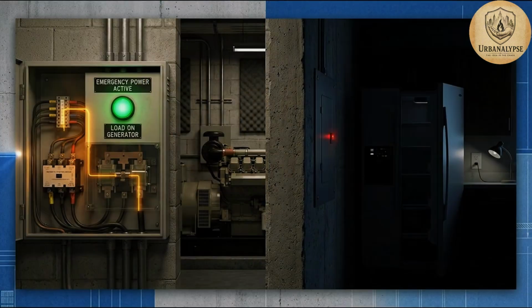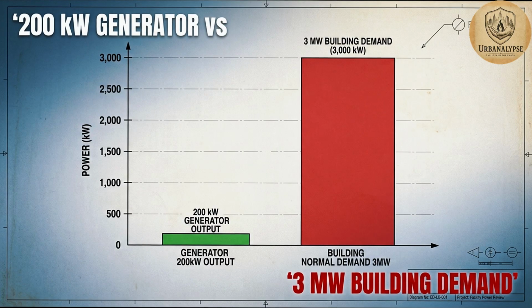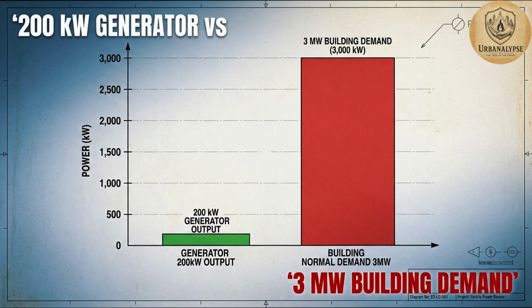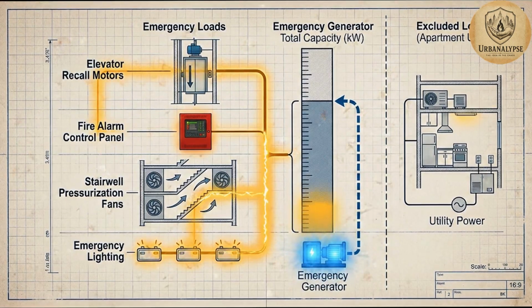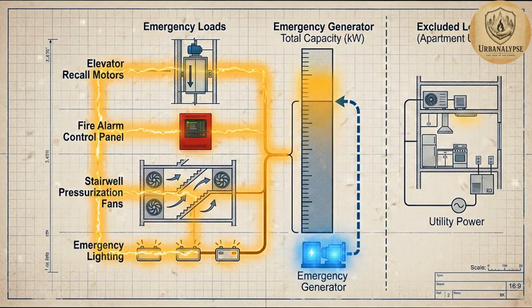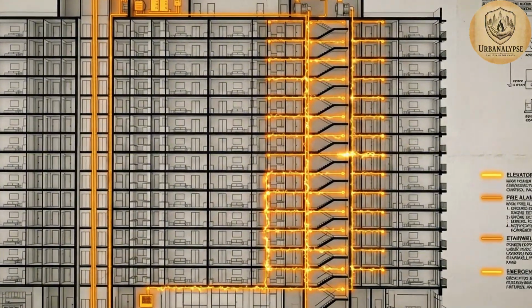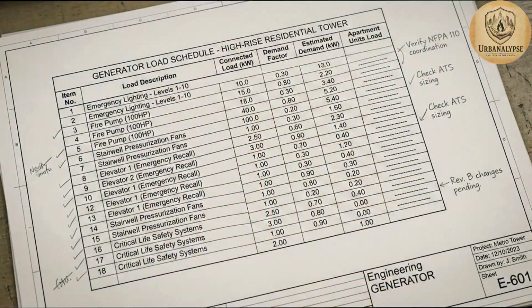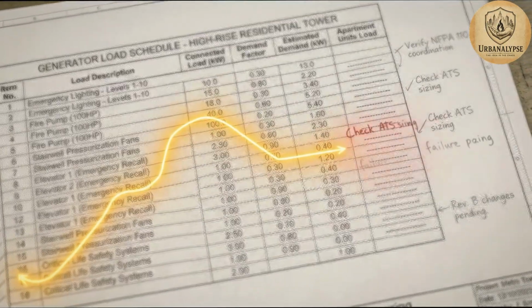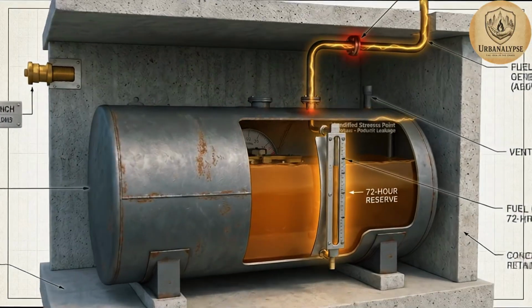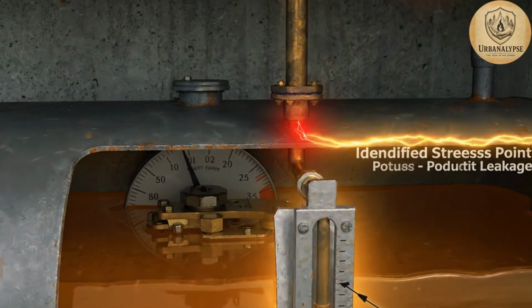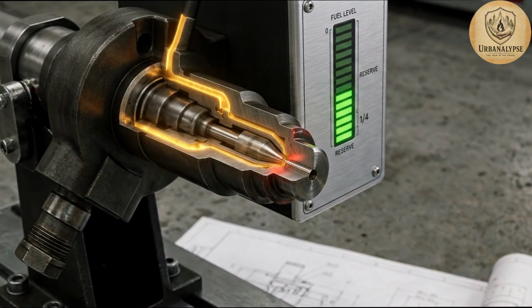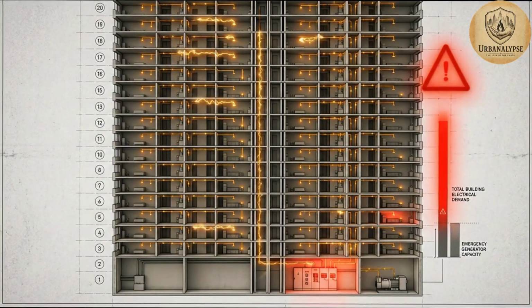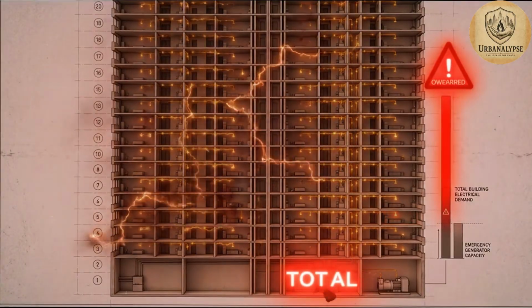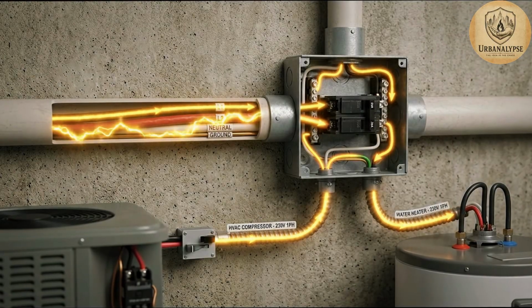Generator sizing standards for commercial high-rise: typical 20-floor emergency generators are sized for approximately 150 to 250 kilowatts of dedicated legal load. Enough to run elevator recall motors, fire alarm control panels, stairwell pressurization fans, and code-required emergency lighting, but only a fraction of the 2 to 4 megawatts a fully occupied 20-floor building draws under normal HVAC and appliance demand. The math itself is the exclusion mechanism, a generator engineered to sustain life safety systems for 72 continuous hours, running on a finite diesel reserve stored on site, cannot also carry 200 apartment units each pulling 230 V single-phase current for refrigerators, water heaters, and air conditioning compressors simultaneously.